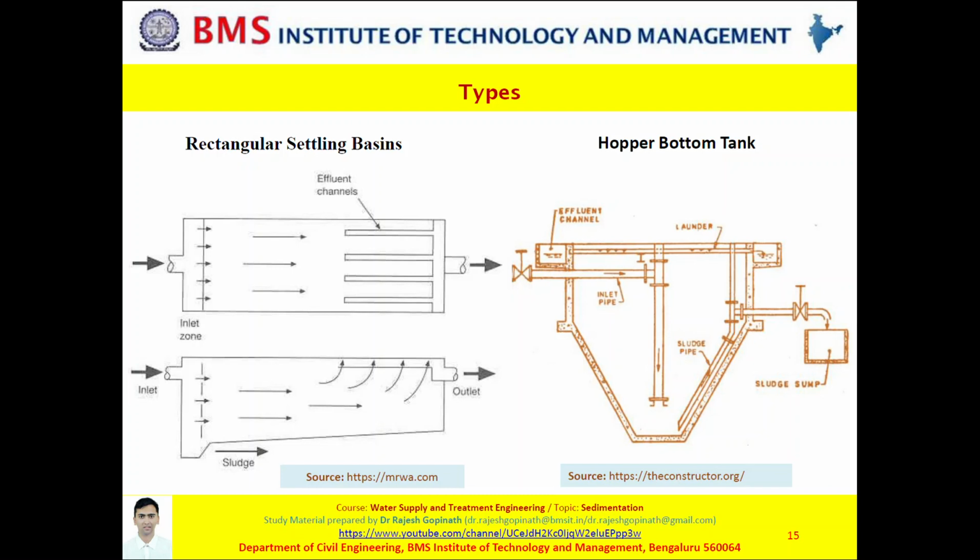Also, a deflector box has been provided at the top which will deflect the influent, that is the incoming water coming from the central pipe, downwards. Eventually, the collected sludge is disposed through a sludge pump and the clarified water is removed through the outlet channel.